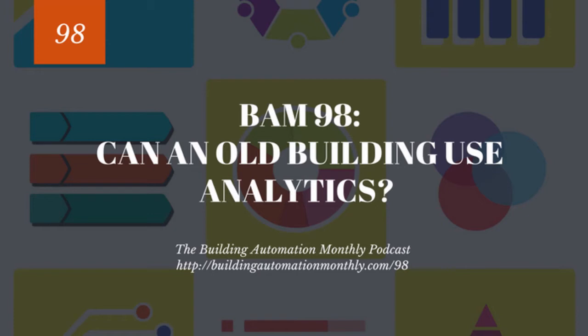What's going on? Well, let's take a look at what analytics really is. So an FDD platform augments your building control system. What's an FDD? Fault detection and diagnostics. So we are able to take the building control system points, all of them. So we're not choosy in terms of specific inputs or outputs. We take them all, along with variables and so on that are built into the system, set points, occupancy points, and the like. We send them to the cloud, 5-minute intervals, and every single point is trended.